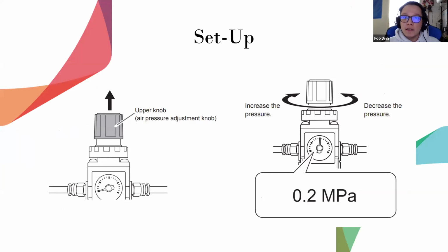Okay, setting the air pressure for the regulator is very, very important. If we put too much, it will cause issues. If we put too little, we're not going to get enough air pressure to blow away the zirconia dust as it's milling. Okay, the pressure we need to set it at is 0.2 MPa.